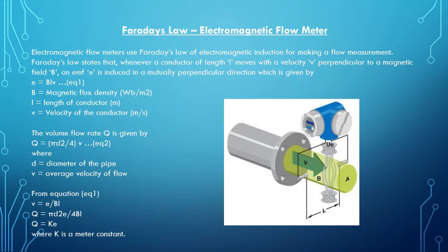Magnetic flow meters work based on Faraday's law of electromagnetic induction. According to this principle, when a conductive medium passes through a magnetic field, a voltage is generated which is proportional to the velocity of the medium, the density of the magnetic field, and the length of the conductor.